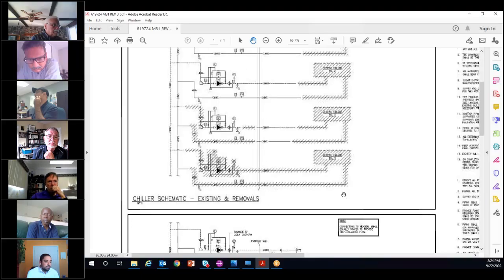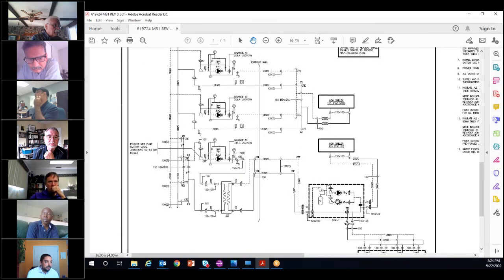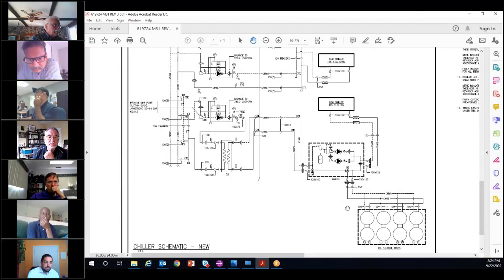So whenever you introduce ice storage, obviously glycol needs to be introduced into the system. These ice storage tanks work on the principle of using your chiller to make sub-freezing glycol at night or whenever needed, depending on your strategy, to freeze the tanks. Within the tanks, there is a skeletal network of plastic tubing with water on the outside. So the tanks are full of water with these tubes inside them that the glycol runs through. So you run sub-freezing glycol through the tubes. That freezes the water on the outside of the tubes until you essentially have a solid block of ice.